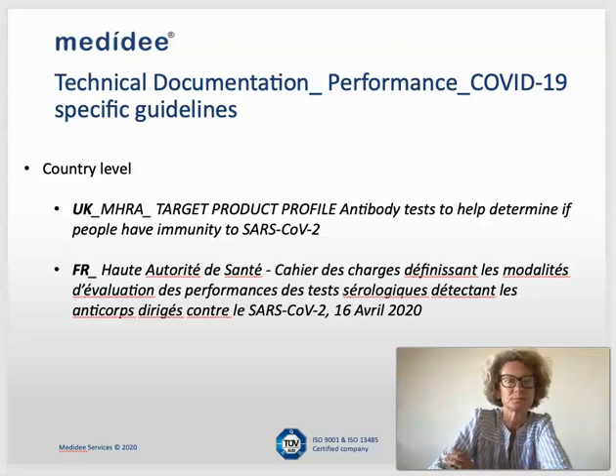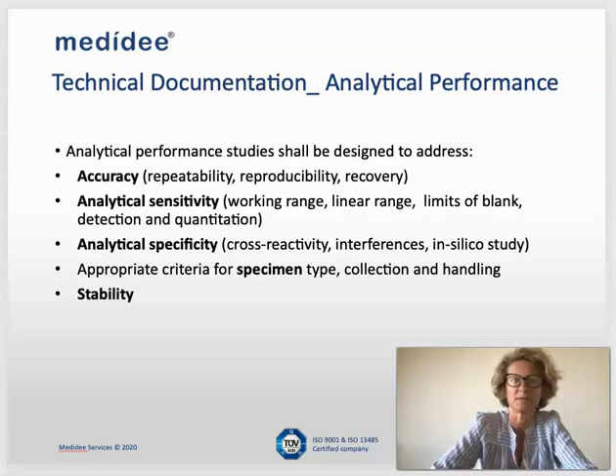The performance of a test is given by its analytical and clinical performance. The analytical performance studies may have different aspects. We can check the accuracy of the test in terms of repeatability, reproducibility, and recovery. Its analytical sensitivity, meaning what is the working range of analyte that can be measured, what is the concentration in terms of linear range, and what are the limits of blank, of detection, and of quantitation. We can also talk about the analytical specificity of the device, how specific the device is in recognizing a specific analyte. And we can have appropriate criteria for specimen type, collection of the specimen, and also handling. And finally, we are also talking about the stability of the device.